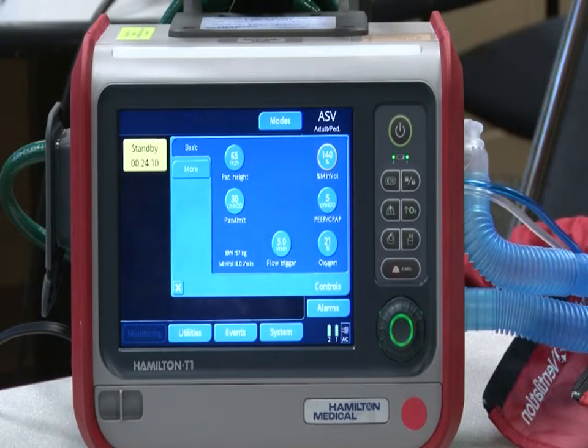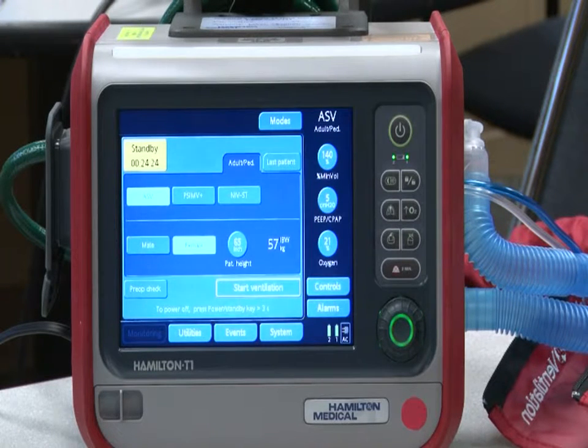So the way that we're going to dial in or order the minute volume we want is by turning that percent minute volume control. Anytime you activate a control variable on the ventilator, it's going to show you at the 7 o'clock position and the 5 o'clock position what the minimum and the maximum value is that you could set that control variable to. So what's the minimum value that I could set that control variable to? 25. Okay. What's the maximum PEEP that I could set this ventilator to? Got it. So you never have to guess about how high or how low can I go? You just touch the button and it'll tell you.